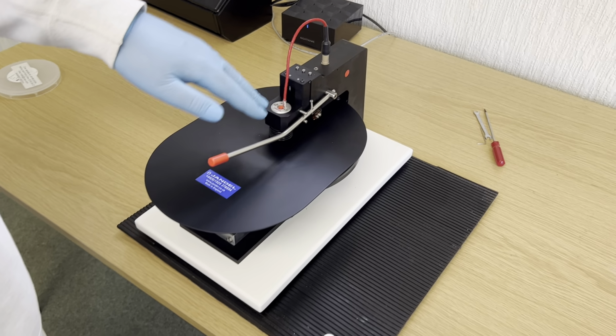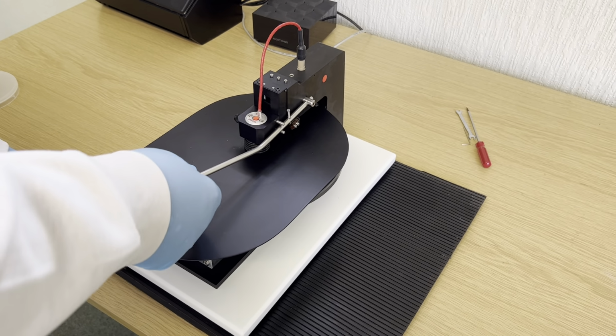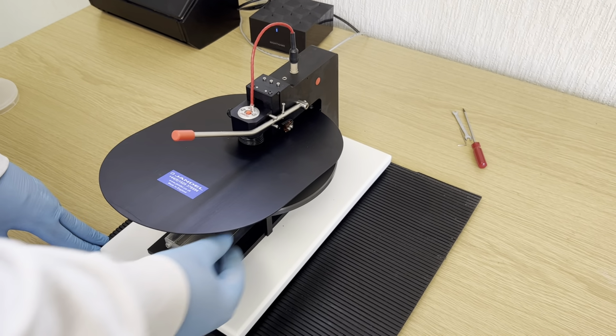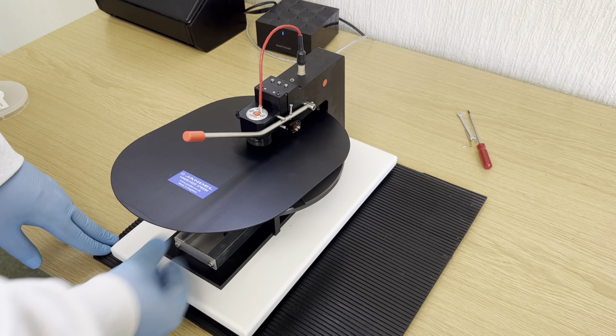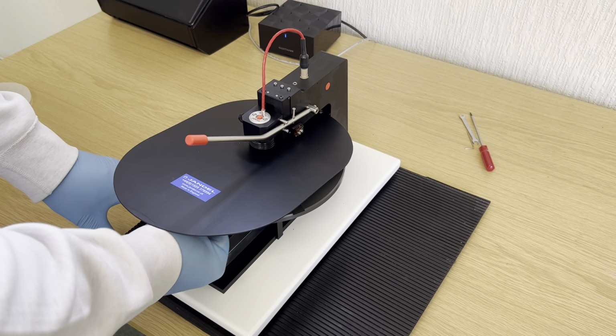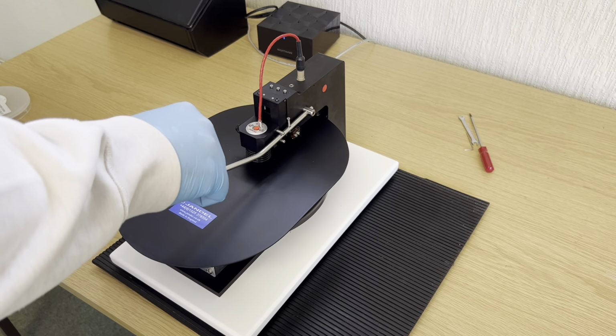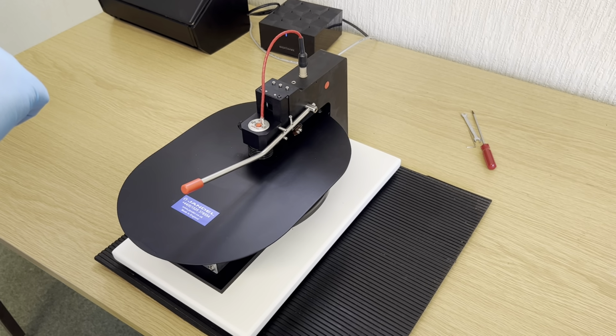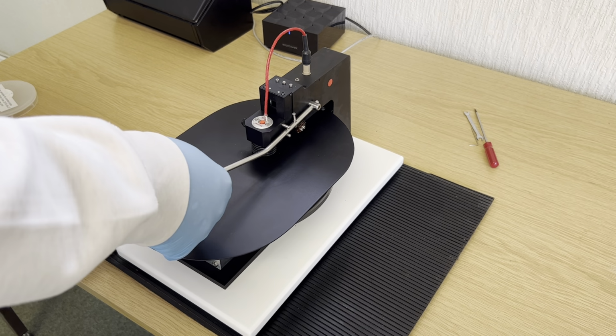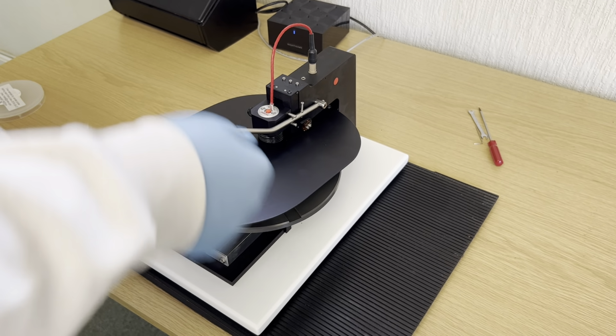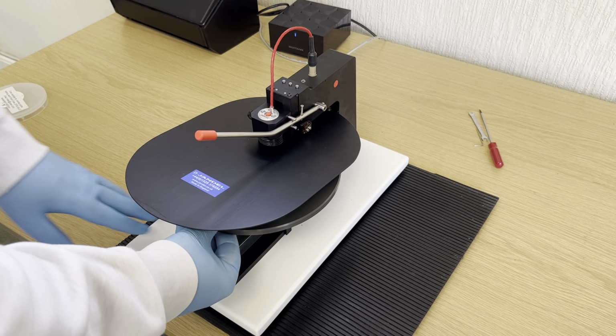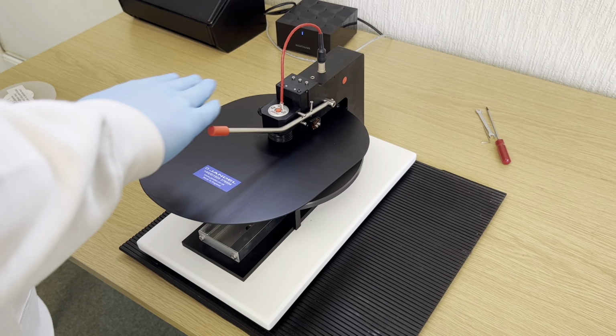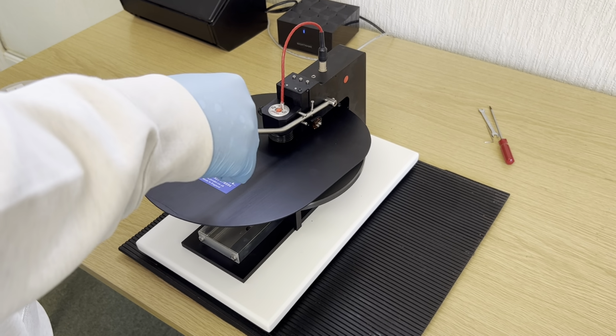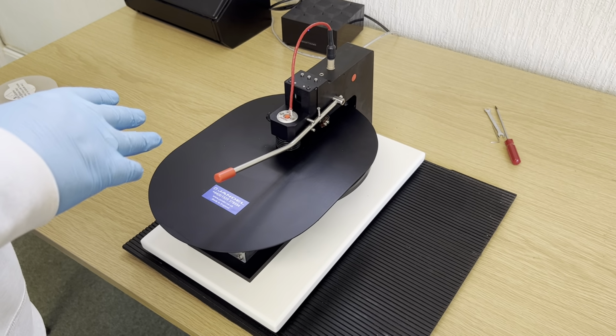The probe's now set for the height of all samples of that thickness, so when it's raised and the sample is moved either rotationally or longitudinally, the probe will go back onto the sample and the needles will again be fully compressed on that sample. It's important to note that whenever moving the sample, whether rotationally or longitudinally along the axis, you must raise the probe head, because otherwise the probes will scuff on the surface and it could damage the probe or the sample.